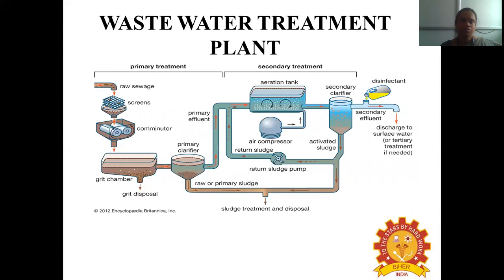This shows the schematic diagram of a wastewater treatment plant. First, raw sewage enters the screening process, which comes under preliminary treatment. Then we have the comminutor, a device which converts large pieces of floating material into smaller particles. Next comes the grit chamber, where grit particles like sand, silt, or metallic salts are removed. The grit is separated and disposed of separately.